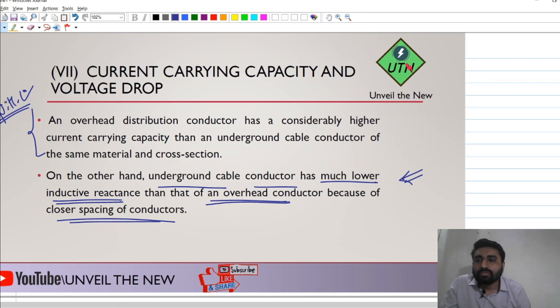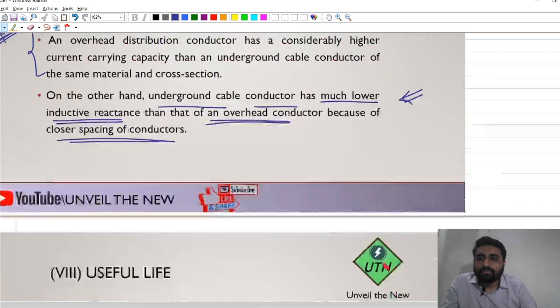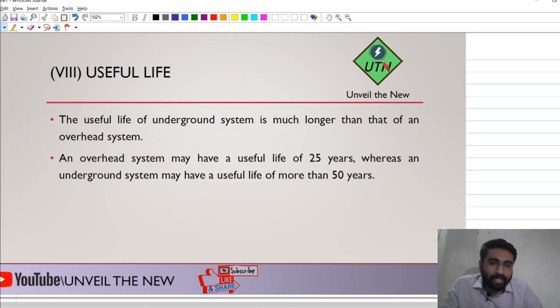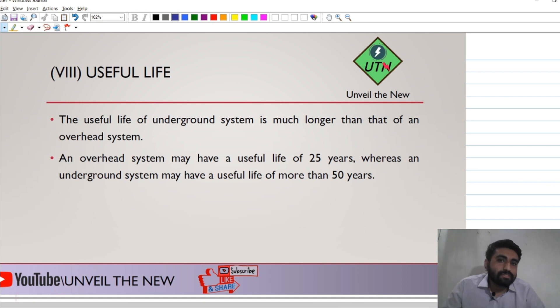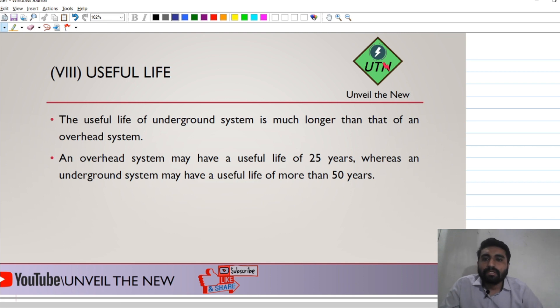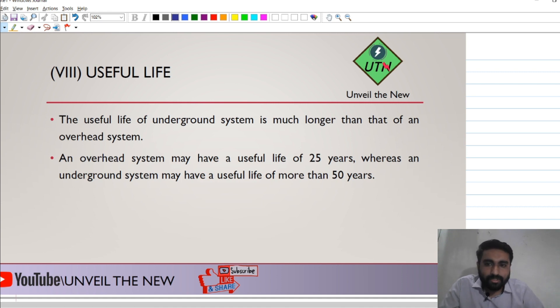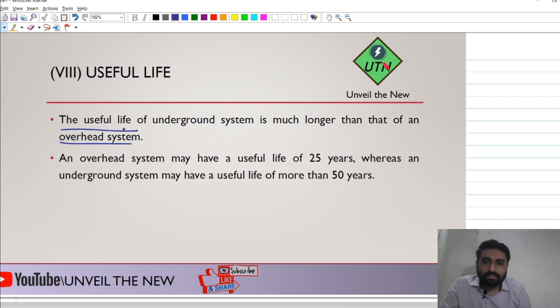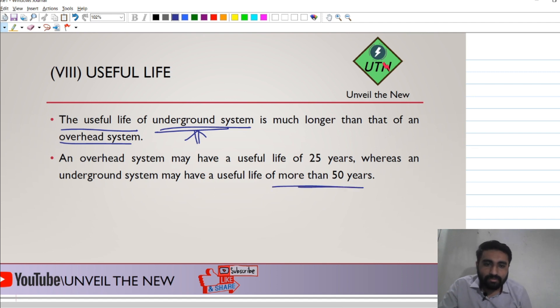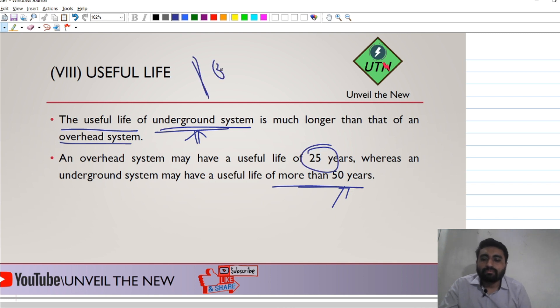Regarding useful life, the underground system has a longer life than the overhead system. Because it is beneath the ground, environmental issues do not affect it as much. External factors have minimal impact on the underground system. The useful life of the underground system is around 50 years, while for the overhead system it is about 25 years. So in terms of useful life, the underground system is the winner.